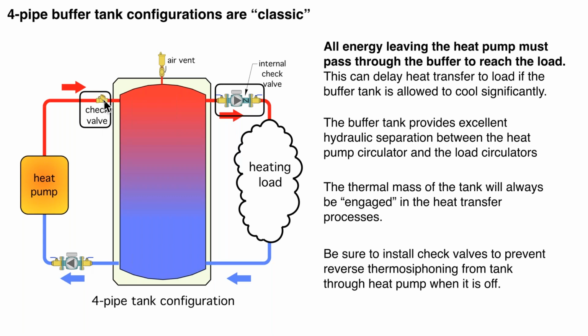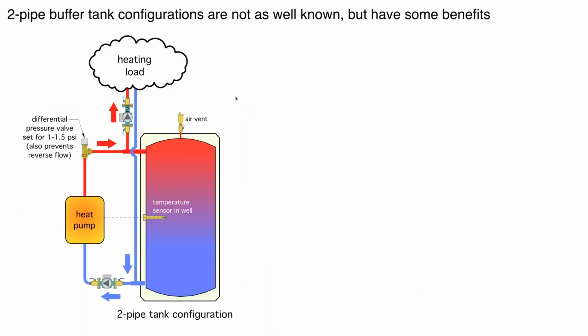So I'm showing here a swing check valve, and also over here, this circulator, just to show something different. Many of the small circulators today are supplied with a small check valve insert that has a spring on it, and that spring will open at roughly about half a PSI. So that's sufficient to block that. In this case, it would be forward thermal siphoning when the circulator is off. Okay, so those again are a couple important details for any hydronic system with a buffer tank.